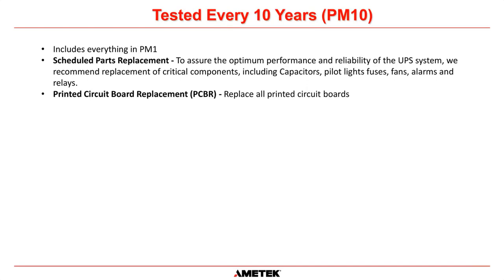And then for a 10-year PM, we will do everything that's in a PM1, and then we will replace all the regular parts: the pilot lights, fans, and relays, but we will also replace capacitors because of the slide that we mentioned earlier. At the 10-year point, the manufacturer recommends we replace those capacitors. And then also we replace the printed circuit boards inside the system because those printed circuit boards have capacitors on them as well. So remember, what we're trying to do is ensure that the reliability of the UPS can be trusted, and we're not going to have any failures as much as we possibly can.